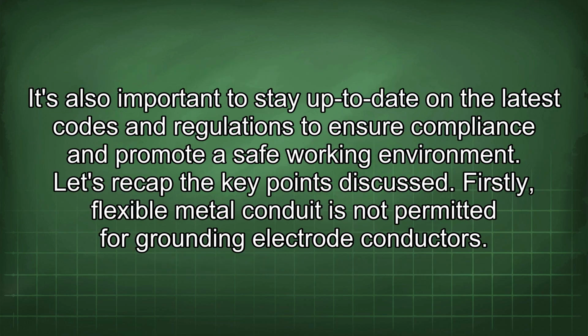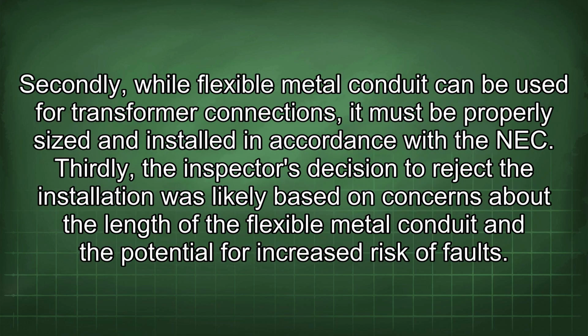It's also important to stay up to date on the latest codes and regulations to ensure compliance and promote a safe working environment. Let's recap the key points discussed. Firstly, flexible metal conduit is not permitted for grounding electrode conductors. Secondly, while flexible metal conduit can be used for transformer connections, it must be properly sized and installed in accordance with the NEC. Thirdly, the inspector's decision to reject the installation was likely based on concerns about the length of the flexible metal conduit and the potential for increased risk of faults.